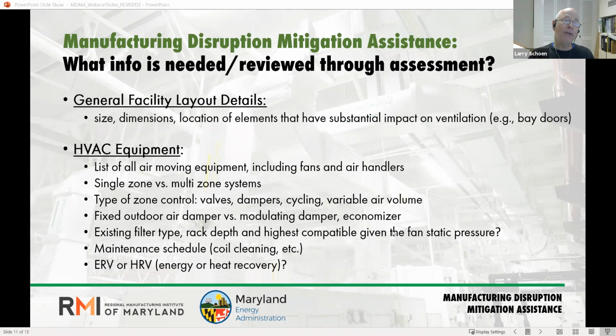Is it a makeup air system where it's constant and running in conjunction with exhaust? Is it part of a mixed air ventilation, recirculating some and injecting in some outdoor air? Does it have an economizer, which in this gorgeous weather right now would pull in 100% outside air, at least when we break above 55 degrees, perhaps. And then looking at the filtration that's available and general maintenance condition, is the system still maintainable?